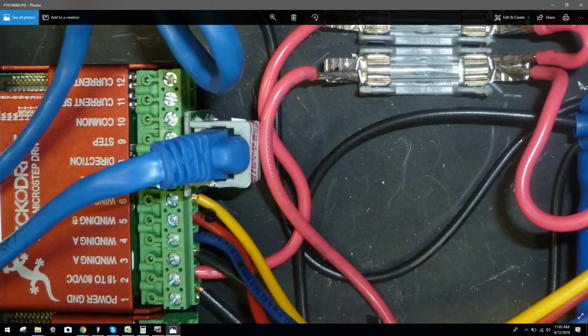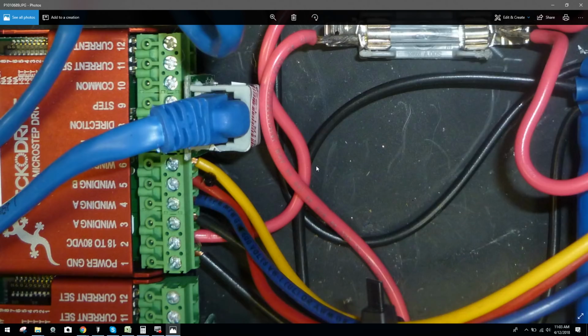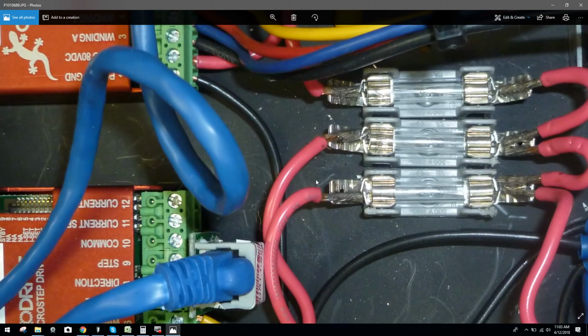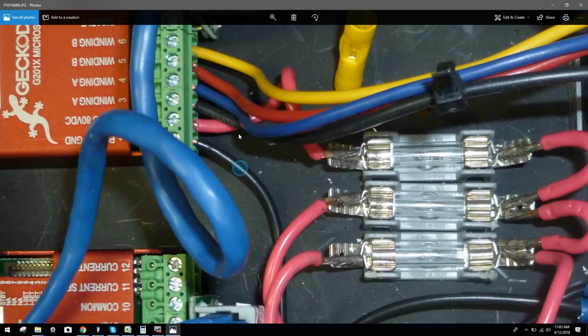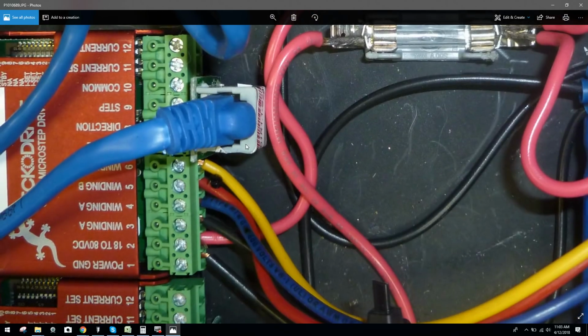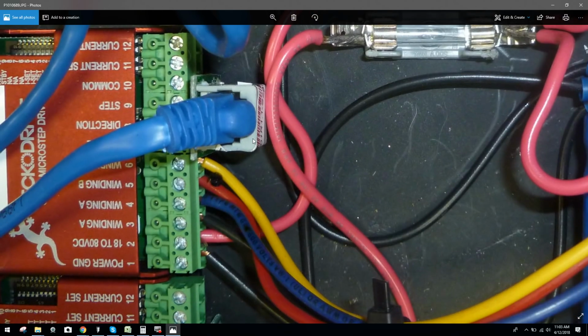But when I see here that these leads aren't even fully inserted in the terminal block, it's frightening, especially considering these are the drives. Look at this. Same thing here, here, here, here, here. We have no idea if all these terminals are working correctly. Yet over here, this one's fine. Well, none of these are correct. It's just baffling to me. It really, really is baffling to me.